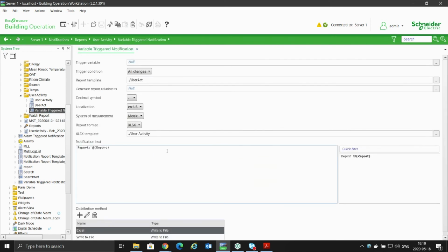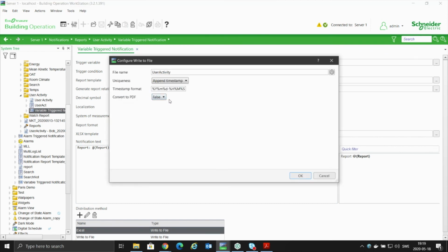As part of the compliance pack, you get a couple of licenses. You get the change control license, you get the TimescaleDB connectivity, or the external log storage license for Timescale, and you get a license for PDF signing. So here you specify you want the result converted to PDF. The next checkbox is for signing of the PDF. It's an option you can turn on that will apply a digital signature using a digital certificate to the PDF report that can then be used to validate that the content has not been altered or edited after the report was generated. And here's where you turn that feature on.